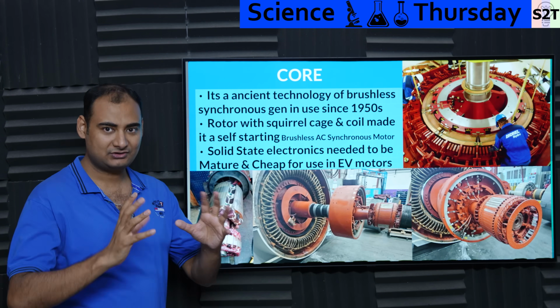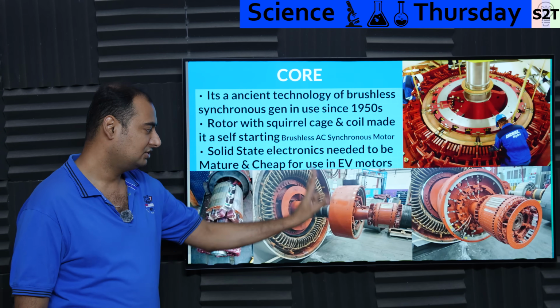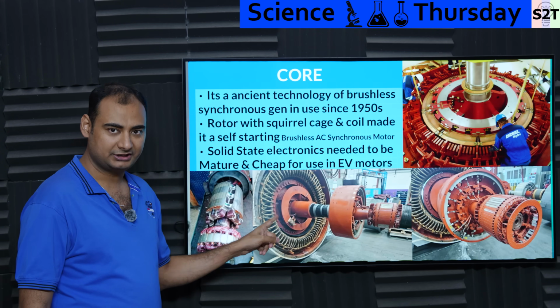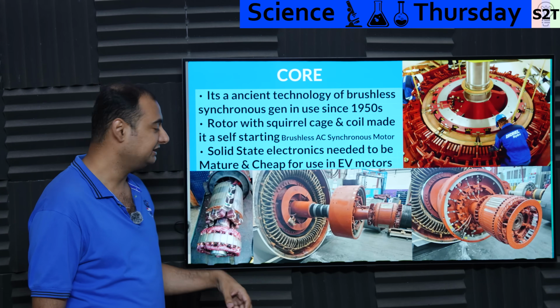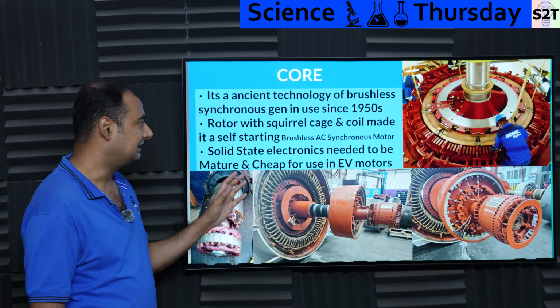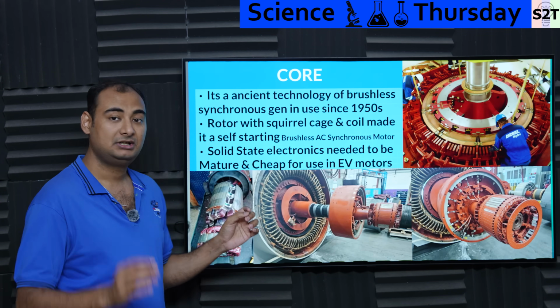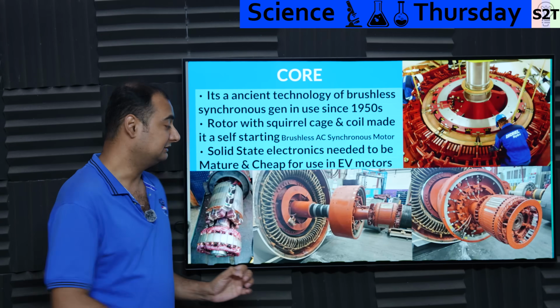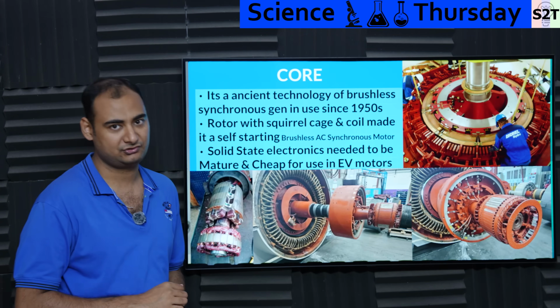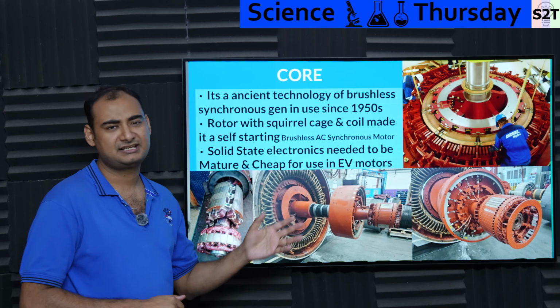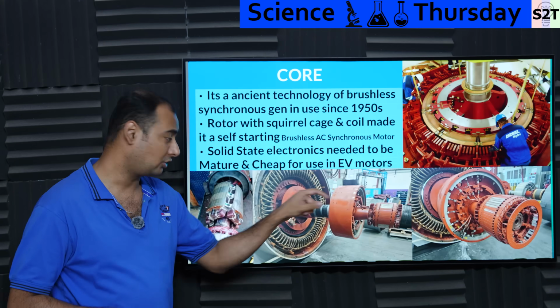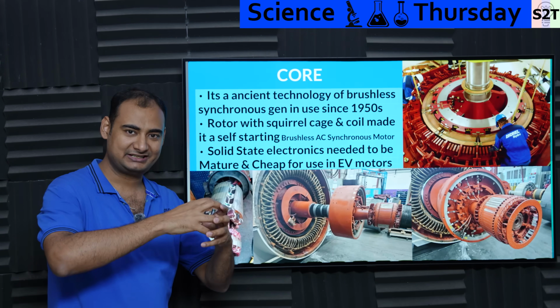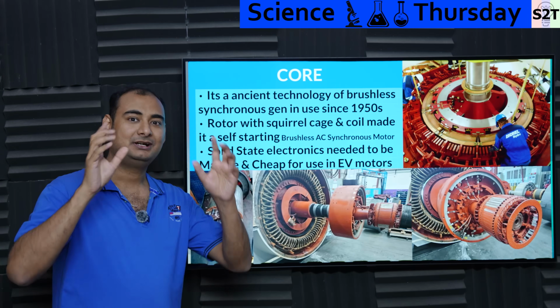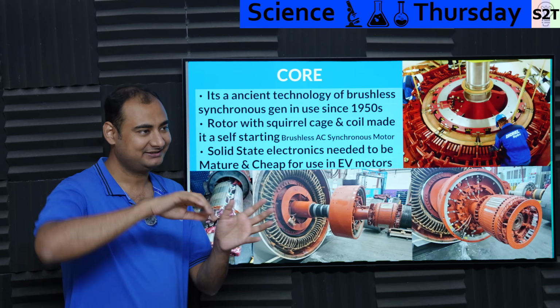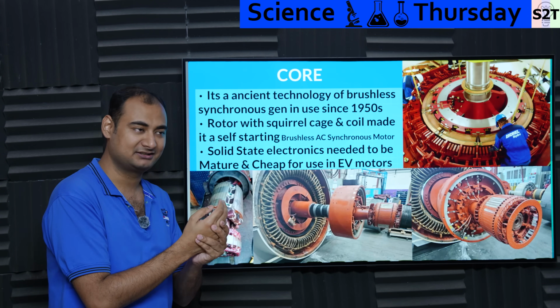So we started with the philosophy of basically having an exciter, a spinning diode, and a rotor that creates the actual magnetic field, and the stator - that was done in 1950. Be mindful, we could have done this earlier, but there was no technology to make spinning diodes robust enough. There were some designs where they had a permanent magnet generator on the same shaft creating power, and that power was leached off using a mercury arc rectifier, feeding it into another coil.